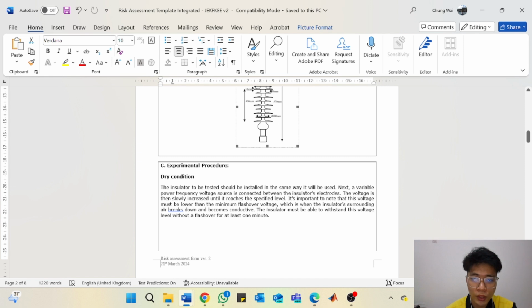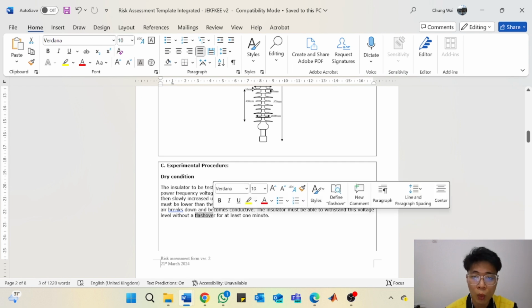So for the experimental procedure, to test the dry condition, the insulator to be tested should be installed in the same way it will be used. Next, a variable power frequency voltage source is connected between the insulator's electrodes. The voltage is then slowly increased until it reaches the specific level. It is important to note that this voltage must be lower than the minimum flashover voltage, which is when the insulator's surrounding air breaks down and becomes conductive. The insulator must be able to withstand this voltage level without a flashover for at least 1 minute.